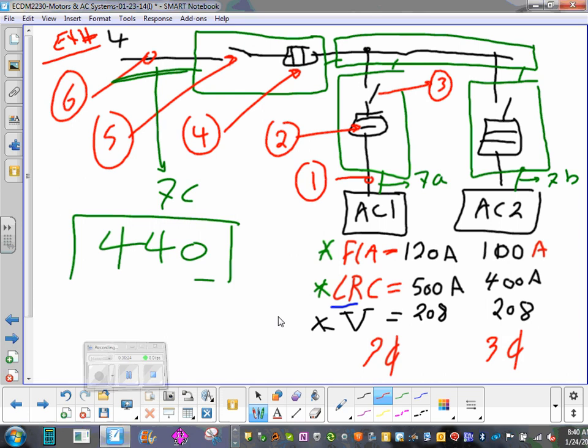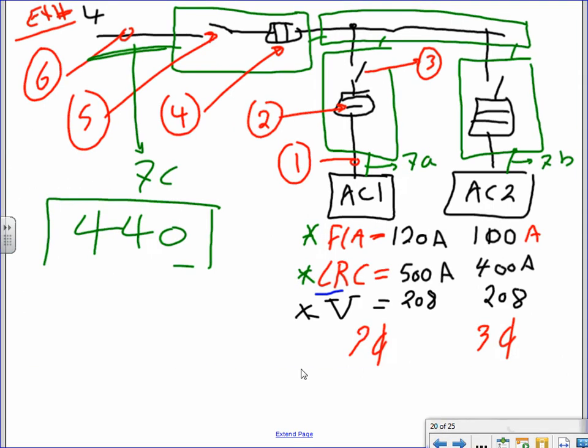Let's go one more time. Same Article 440 setup. We have two chillers: chiller one has full load amp 120, locked rotor current 500; chiller two has full load amp 100, locked rotor current 400. Voltage is 208V, three-phase system.